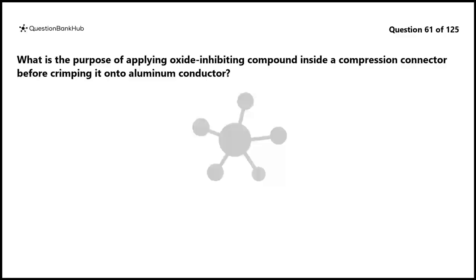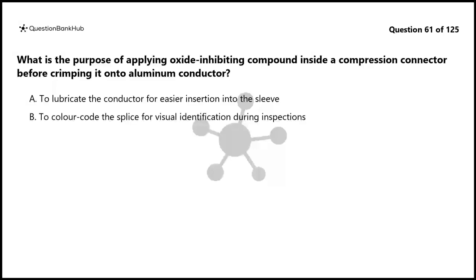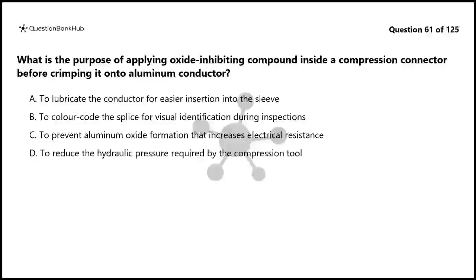Question 61. What is the purpose of applying oxide-inhibiting compound inside a compression connector before crimping it onto aluminum conductor? A. To lubricate the conductor for easier insertion into the sleeve. B. To color-code the splice for visual identification during inspections. C. To prevent aluminum oxide formation that increases electrical resistance. D. To reduce the hydraulic pressure required by the compression tool.